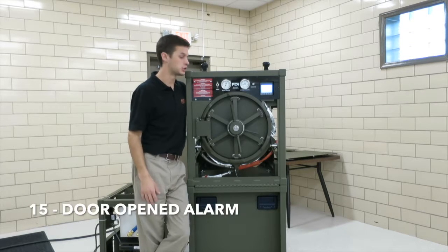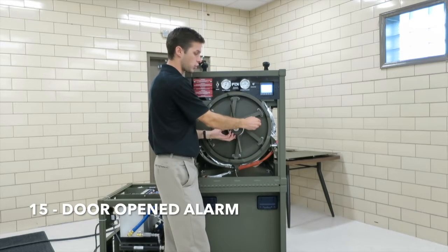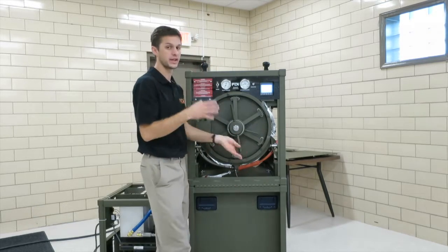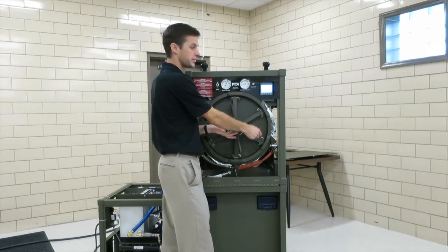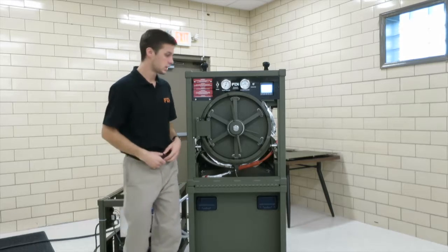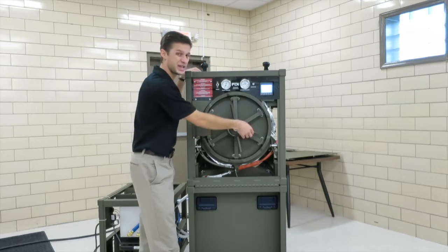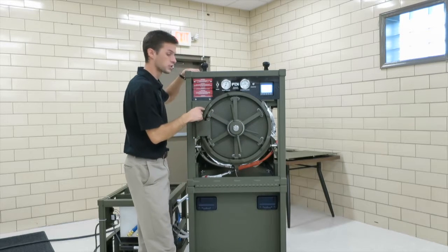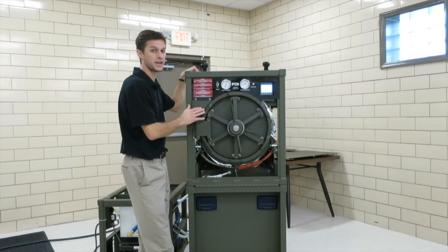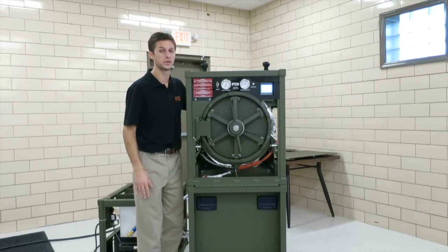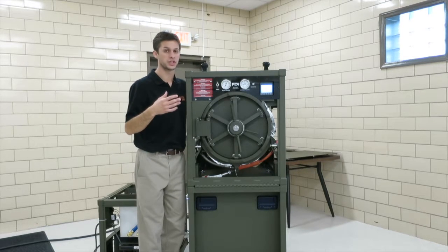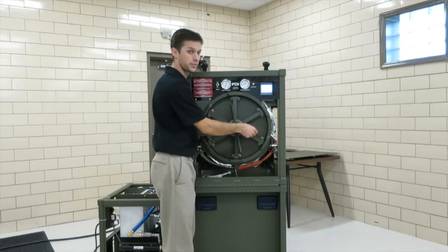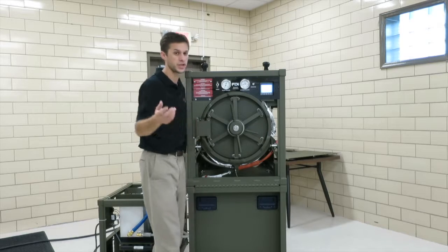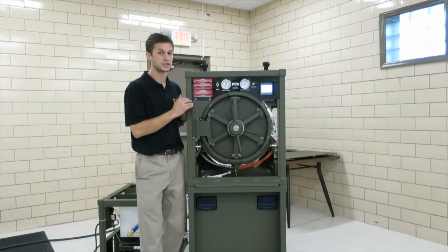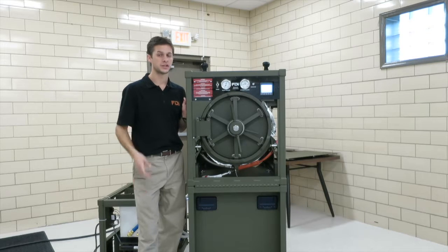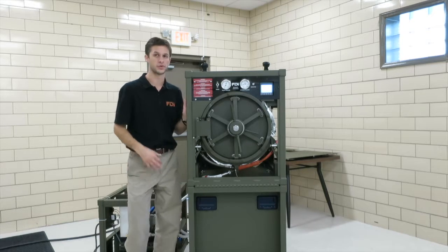Number 15 is door opened. If I ever tried to open this door during a cycle, or when it's venting, at the end of the cycle, if I tried to open it too early, I will get a 15 door open alarm. Also though, if you're getting it and you know you're not doing anything wrong, the door switch sensor could be out of alignment, out of calibration, and there's a procedure in the back of the manual to recalibrate your door switch sensor. So if your operator is saying, I'm not opening the door early, but I'm still getting this door open alarm, then your door switch sensor is possibly out of alignment, and you can reprogram that to get rid of that alarm from reoccurring.